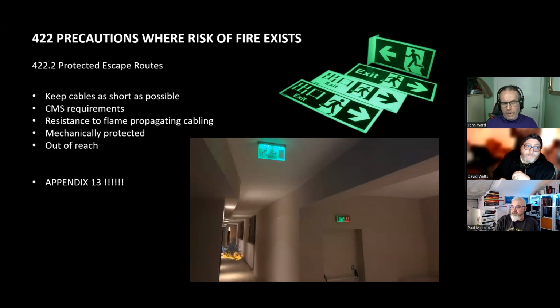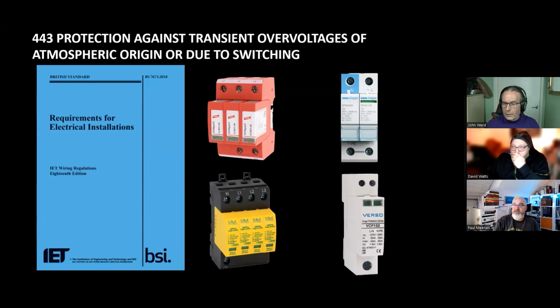So Darren Sloan has said fire alarm panel supply is wired in FP200. I don't, I wire it in FP600. That's me, because I've made a choice to use FP600 mainly, in fairness, because with FP400 you have to buy 5,000 meters of the damn stuff. That's why I went with it. But it's a 2-hour fire survival cable, so that's what I use. And also my UPSs are rated for 2 hours, not 1 hour. So that's why I make that engineering call.